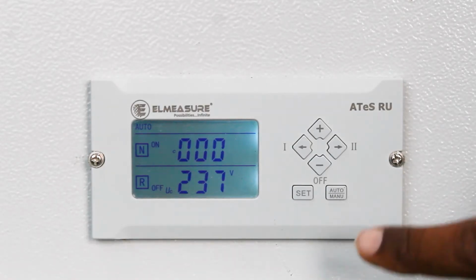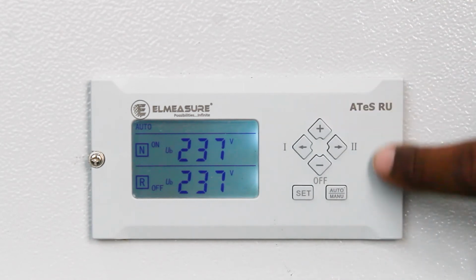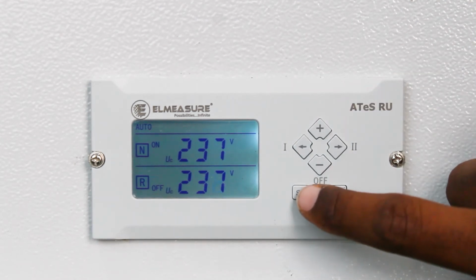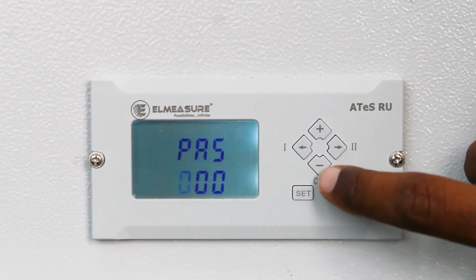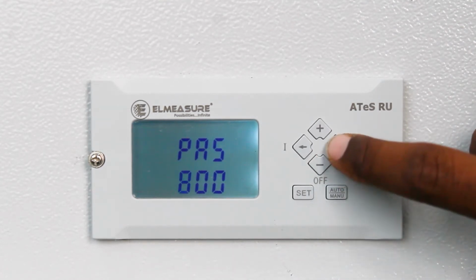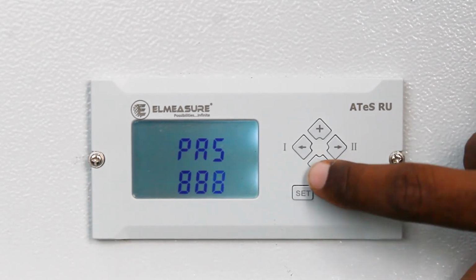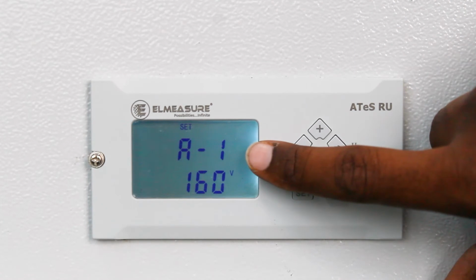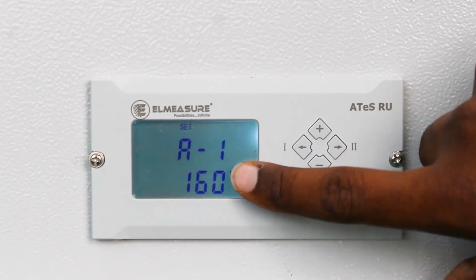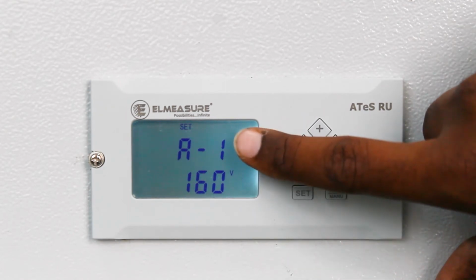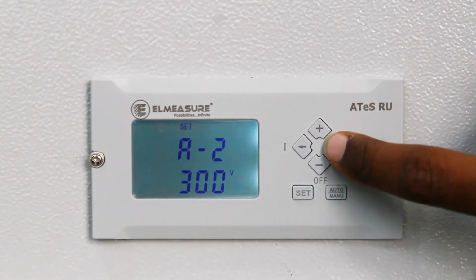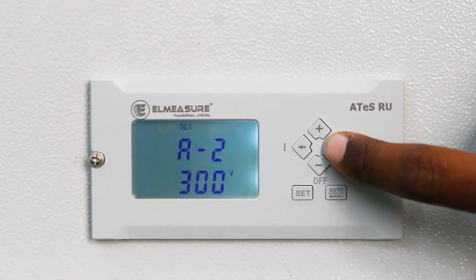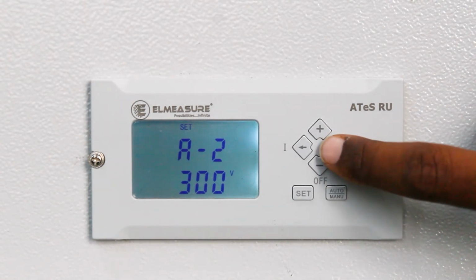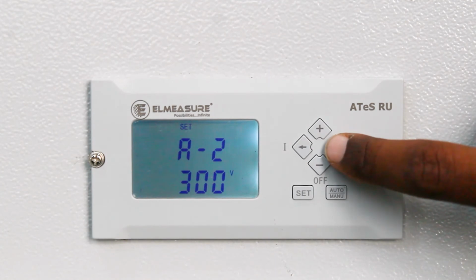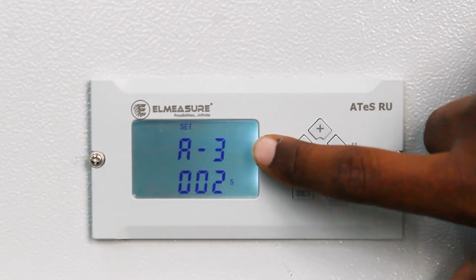Now I am entering the programming menu. Here we have six keys for programming. Now enter the programming menu. The password will be 888. Once it's set, it will move to A1. A1 is transformer under voltage, programmable from 150 to a maximum of 200 volts. A2 is transformer over voltage, and we can program from 220 volts to 300 volts AC line to neutral.